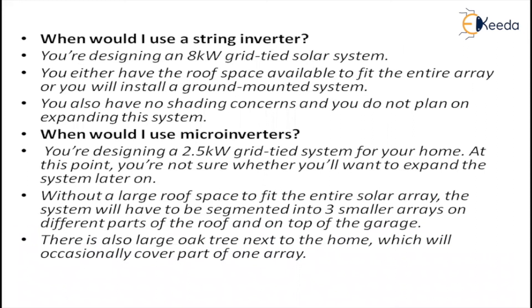When would you use string inverters? If you are designing an 8 kilowatt grid-tie solar system, you can use a string inverter where you have roof space available to fit the entire array, or you can install a ground-mounted system. You should also have no shading concerns and no plans for expanding the system. That is the scenario where string inverters are used.